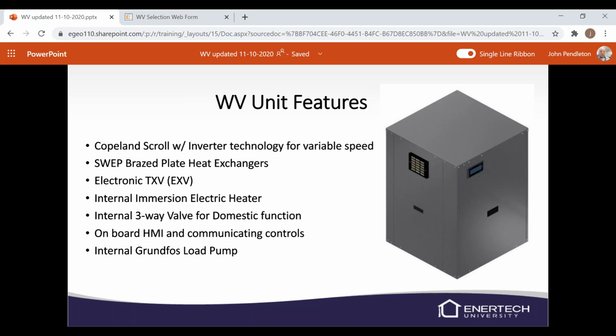Again, we have an internal electric immersion heater for backup, emergency, auxiliary, however you want to look at that. There is an internal three-way valve that will switch from your radiant heating to your domestic hot water function. It does have an onboard HMI, which is a human machine interface. Basically, it's how you do all the setups. You can look at that screen and it'll tell you the operation of the unit. It's right on the front of the unit. And there is an internal Grundfos load pump as well towards the top of the unit.